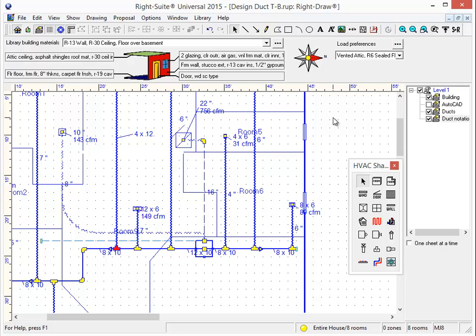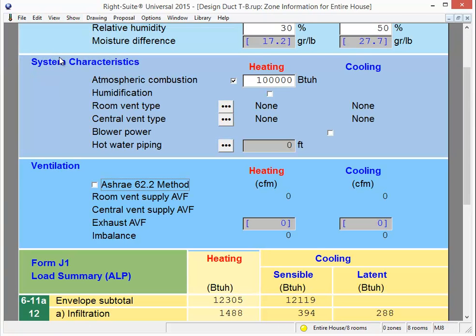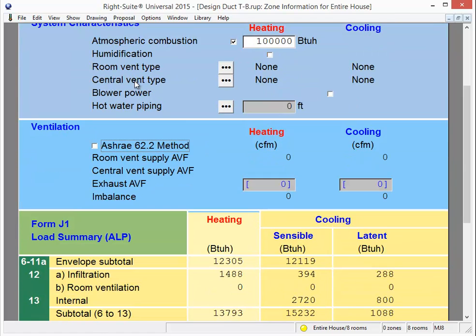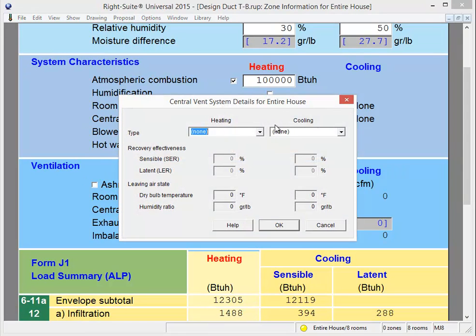The last feature we're going to look at is probably going to be one of our most popular, especially for customers involved with new construction. It's a tool designed to help you do ventilation calculations and comply with ASHRAE 62. As has always been the case, our zone information page is where our ventilation settings are located. So if I go to the Show menu and go to Zone Information, about halfway down the page is where I'll see my ventilation section, although this will also tie in with system characteristics, as that's where I choose what type of ventilation there's going to be.